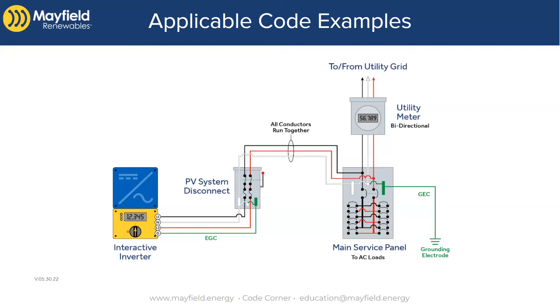It's worth pointing out that all conductors run together. You will have some sort of conduit coming from your main service panel over to the new PV system disconnect. That can be PVC or rigid, and you follow the rules in Article 230 for the wiring method. You bond those as appropriate based on whether it's PVC versus metal conduit.